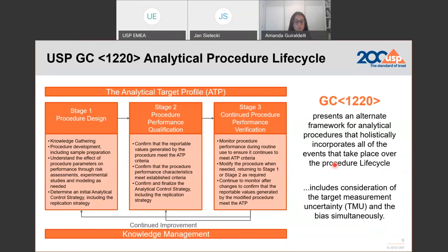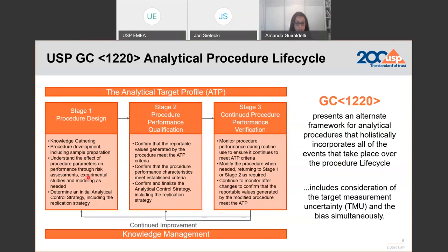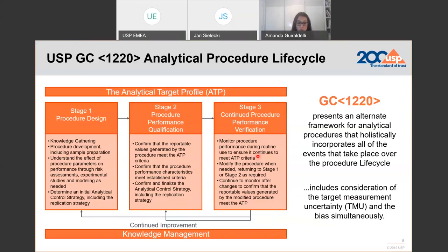Regarding Chapter 1220 on Procedure Lifecycle: this chapter presents a framework where the procedure lifecycle consists of three interconnected stages — stage one: procedure design, which is method development; stage two: validation; and stage three: performance verification. This approach promotes continuous improvement and emphasizes the importance of scientific knowledge and quality risk management throughout the procedure lifecycle, including the estimation of measurement uncertainty and establishing tolerances to support correct decisions about product and method performance.